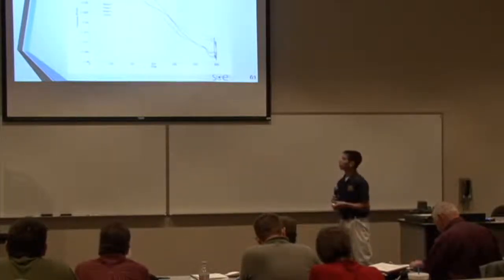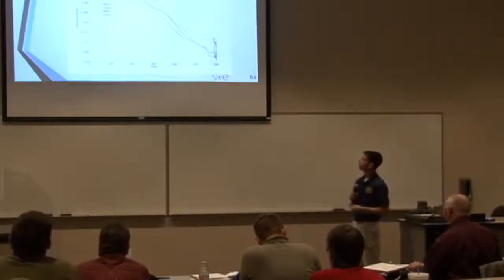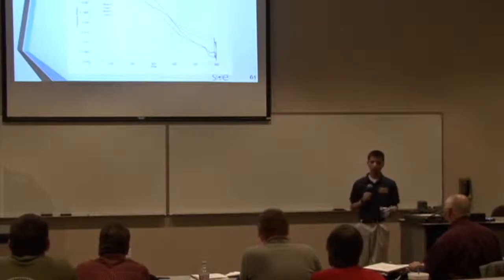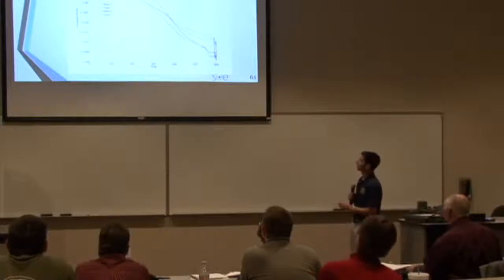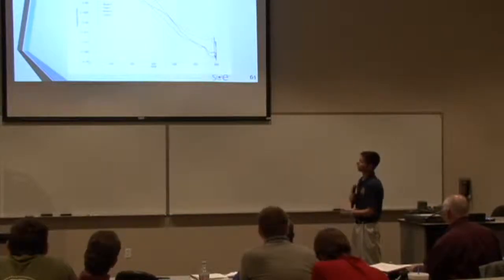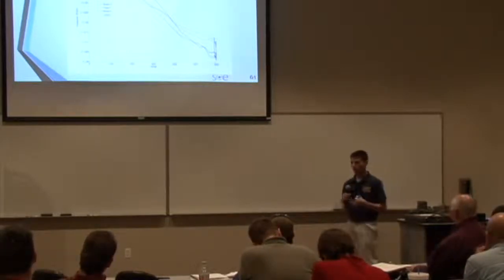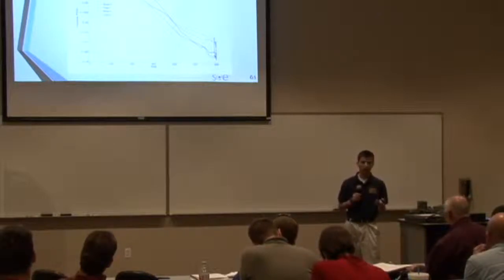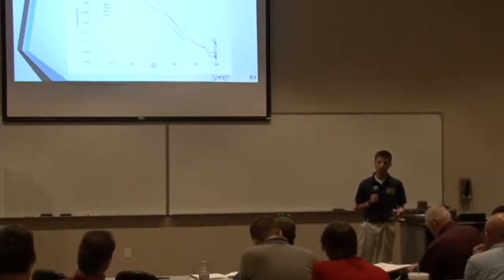So, the actual data. What we can see here from this test, which was from 30 to 600 RPM, was a pressure drop. The blower was not turned on at this point, so we could actually see how the rotation was affecting the pressure measurements. Up until about 200 RPM, we can see that the diaphragms on the pressure transducers tend to stay about the same, and then they begin their decline. The reason is the way that these sensors are situated: when iris is spinning, the diaphragm is forced outward, and that results in a lower pressure measurement at the pressure transducer.